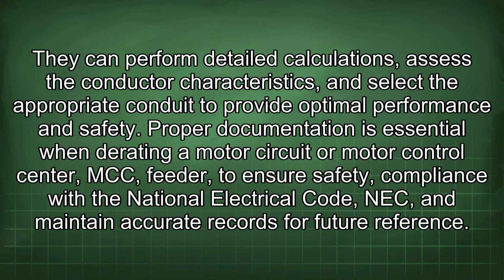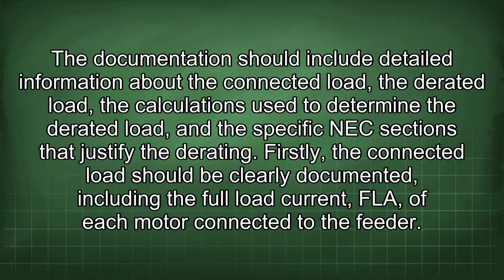Proper documentation is essential when derating a motor circuit or motor control center (MCC) feeder to ensure safety, compliance with the National Electrical Code (NEC), and maintain accurate records for future reference. The documentation should include detailed information about the connected load, the derated load, the calculations used to determine the derated load, and the specific NEC sections that justify the derating.